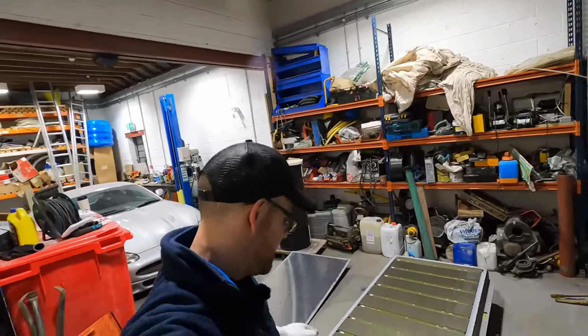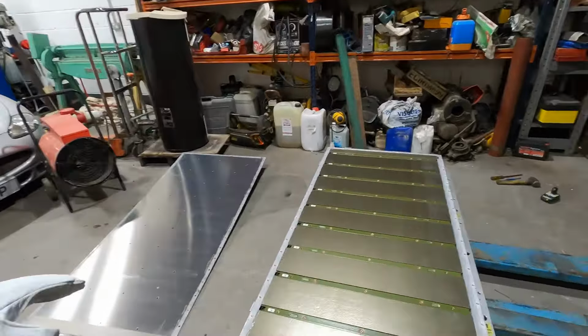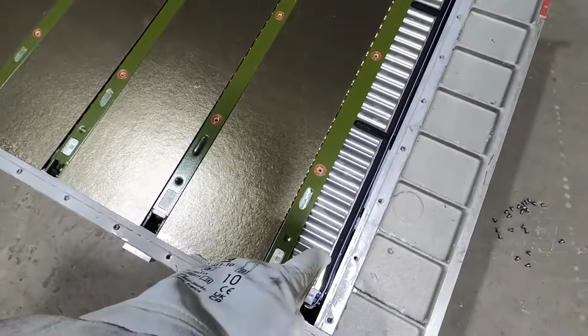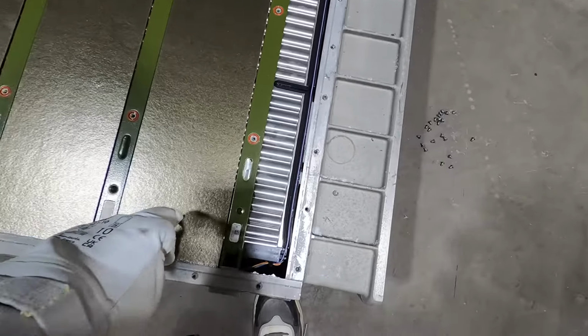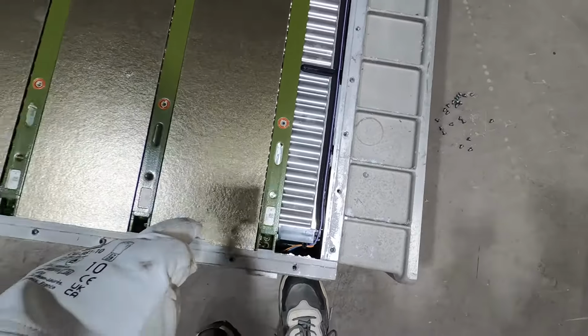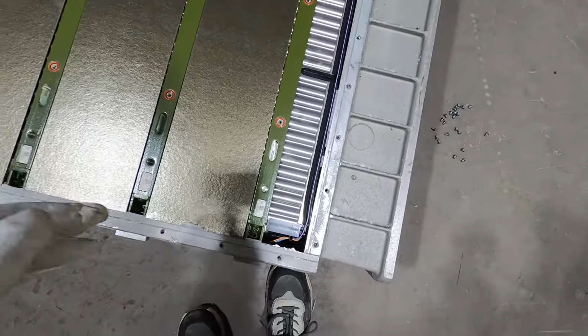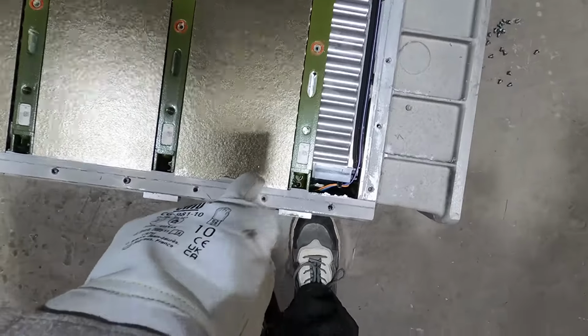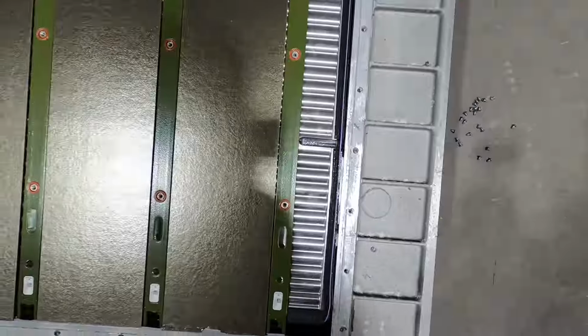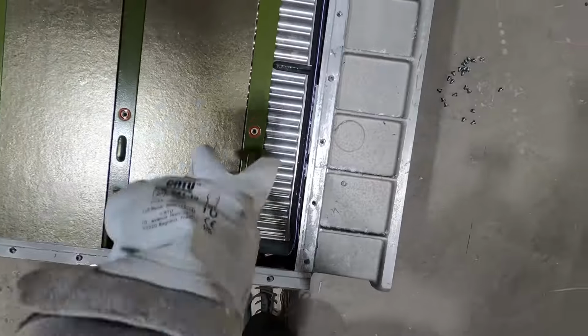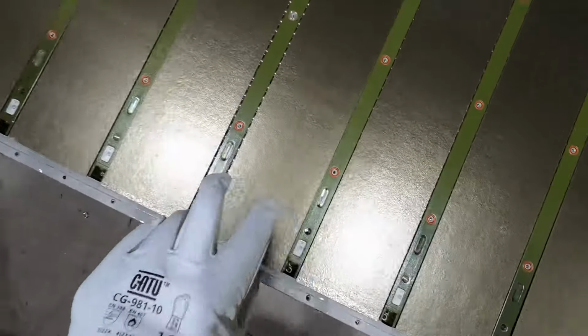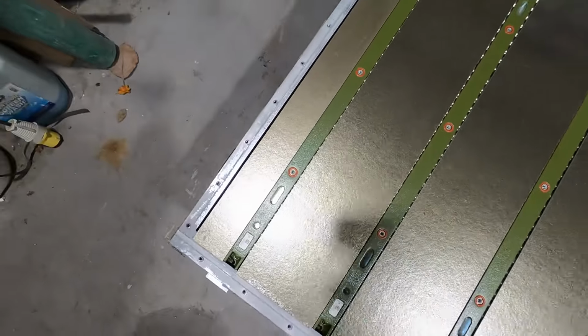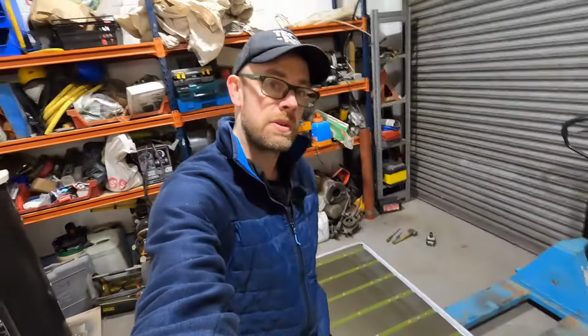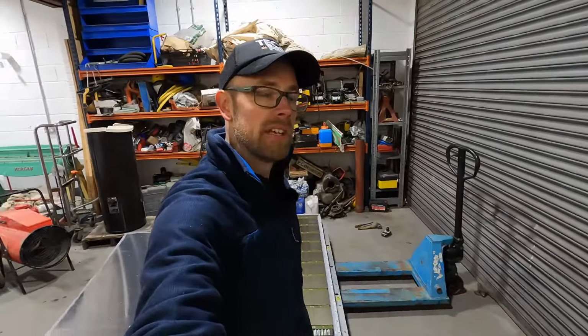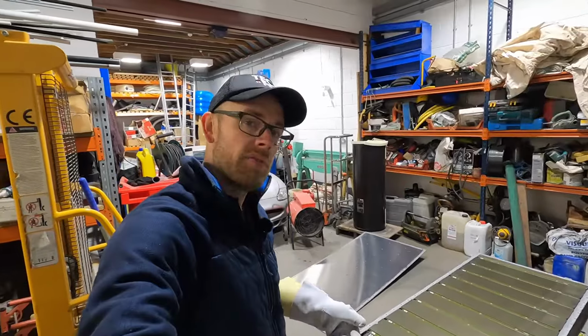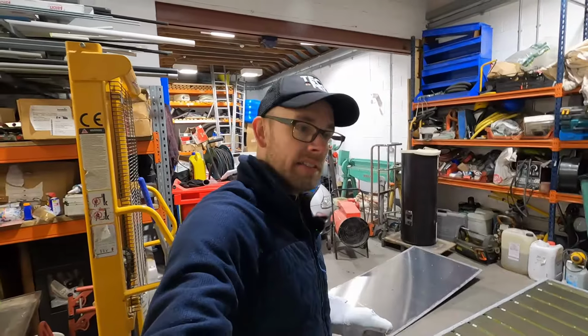So what you can see here is basically there are essentially 10 modules, so you have a bank of cells down one side. These are like a vermiculite panel that increases the fire rating, very thermally efficient, and there'll be another line of batteries down that side, so that's one module. You've got 1, 2, 3, 4, 5, 6, 7, 8, 9, 10 modules. If they're all in series, that makes them 24 volt modules, which is a standard output for these, but I'll take the vermiculite off one of the packs now, see what it's like.